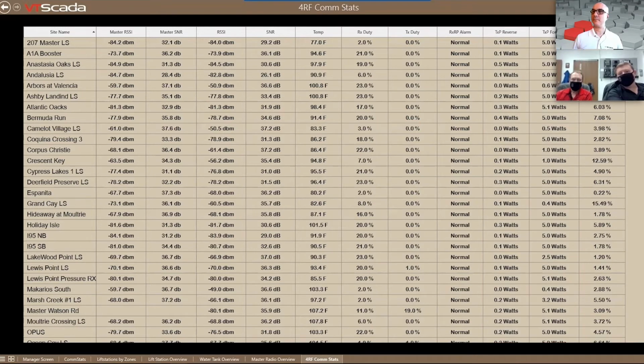On the far right here, it's also got the reflected power, which is one of the key indicators for an ongoing issue with the radio, measured in percent. We have the one column that shows the transmit forward power. Some radios that are closer to the master than others, we don't necessarily need to use the full power, so we can turn the power down on the radio. The transmit reverse power is how much reflective power is coming from the antenna, and that tells us a whole lot about how that antenna is radiating the signal.